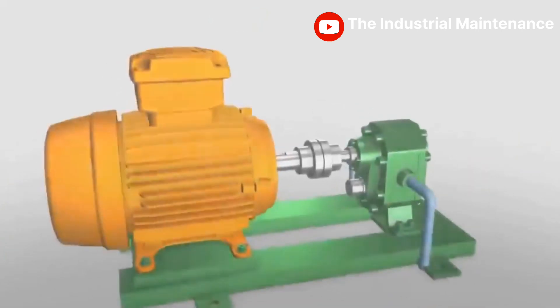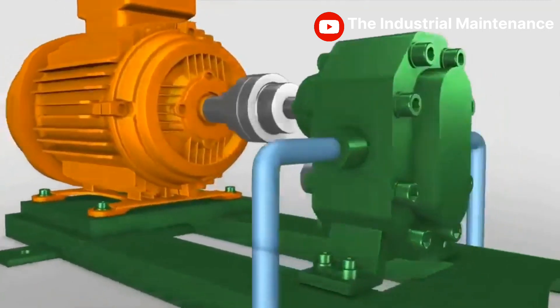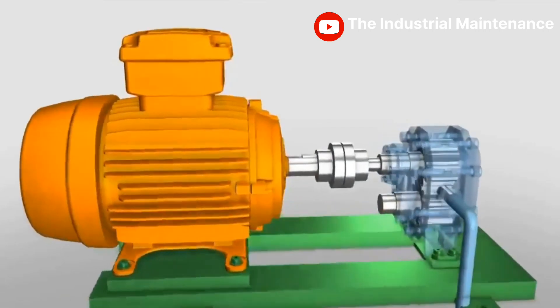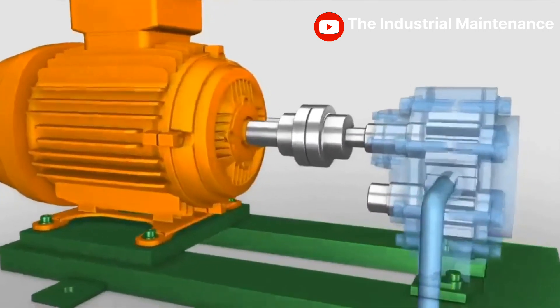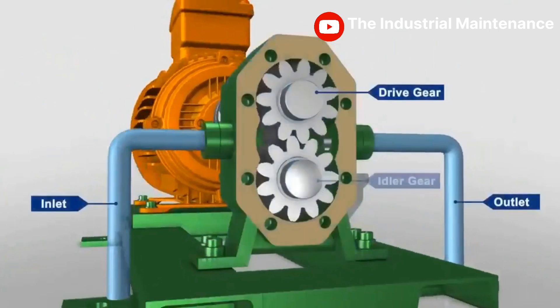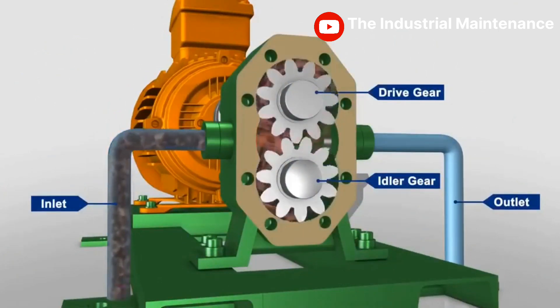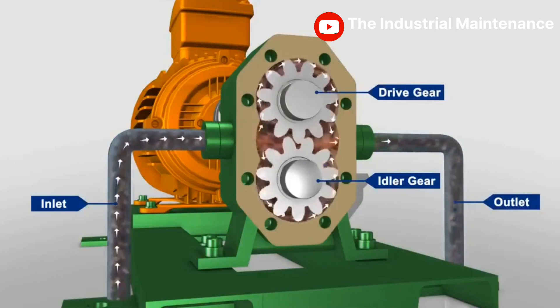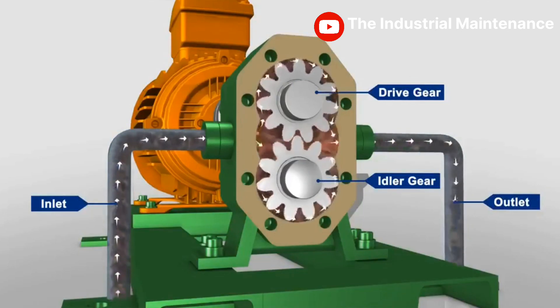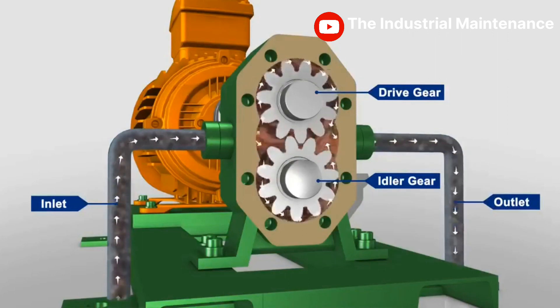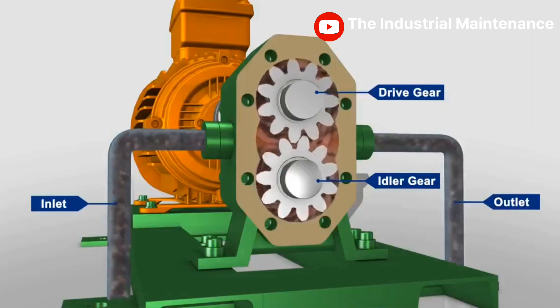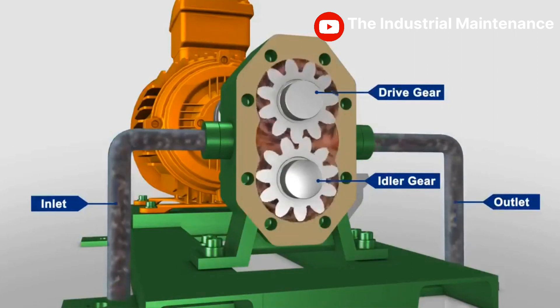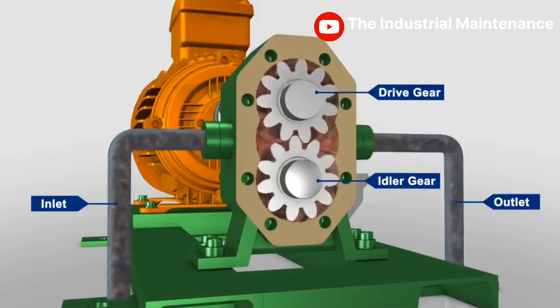The gear pump is so named because it has two gears that are side by side, or external to each other. A drive gear, driven by a motor, rotates an idler gear in the opposite direction. When the gears rotate, the liquid trapped in the gear teeth spaces between the housing bore and the outside of the gears is transferred from the inlet side to the outlet side. The meshing of the gears on the discharge side pushes the liquid out of the pump and into the discharge piping.